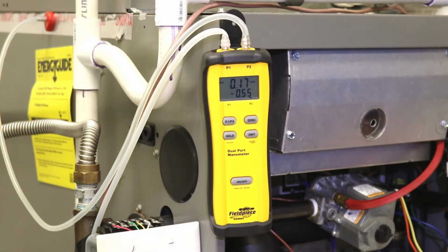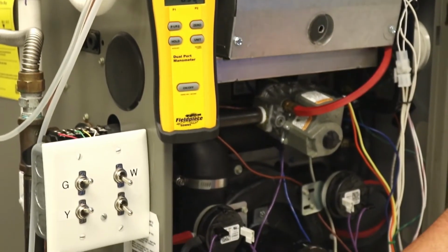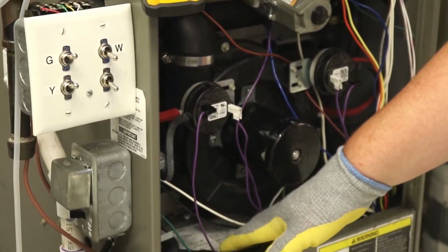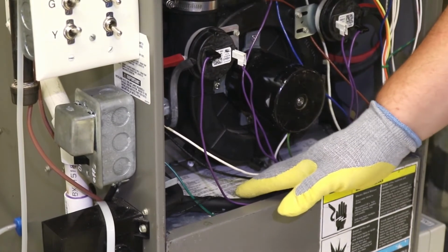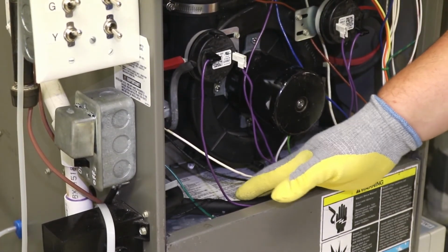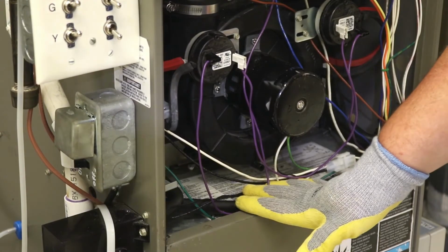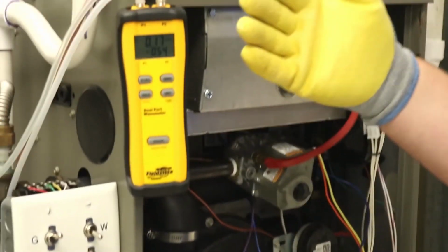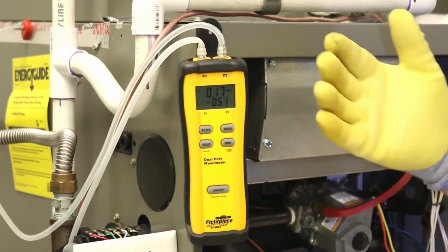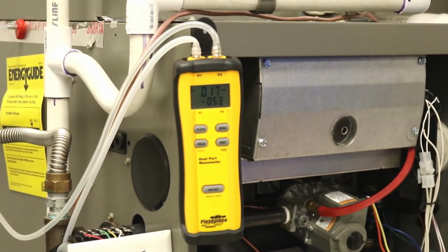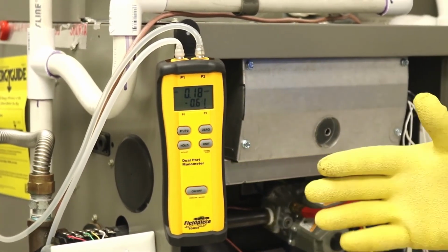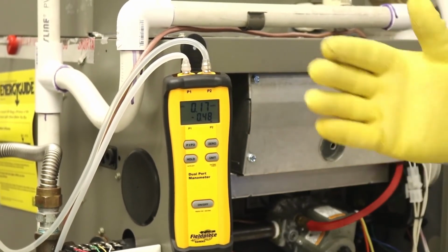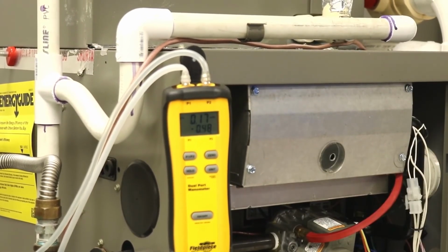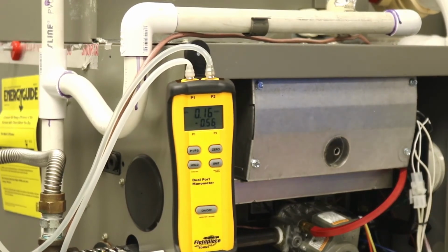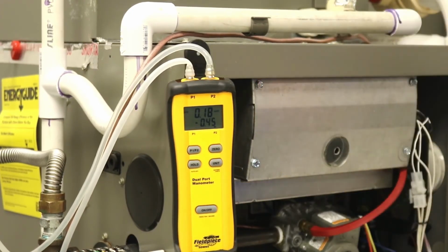You can always find on the equipment from the data plate down here at the bottom, it's going to tell you what the maximum static pressure is for that system. For this particular system, I've taken the liberty of going ahead and checking that out. For this particular system, it is 0.5 inches of water column. So if this number on our manometer were above 0.5 inches of water column, we know that we have an airflow issue. So as you're looking at the system, make sure as it's running, while the equipment is at full bore, that you're not going above that 0.5.